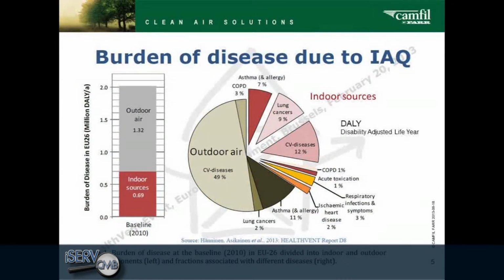And they draw attention to the fact that a lot of the burden of disease in airborne pollution is in fact based in the outside air coming into the building. If you look at this diagram, you can just see here outdoor air accounts for about 2/3 of the burden of disease, and as such it makes very good sense to have good efficient air filtration on the incoming supply air to the building. There are, of course, internally based pollutants that, again, cause health problems, and for that, of course, you would normally have recirculation and filters to deal with that as well.